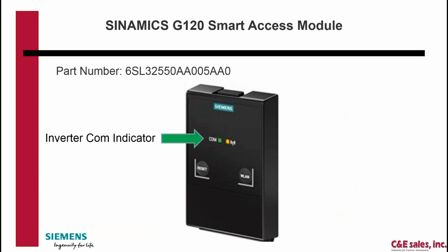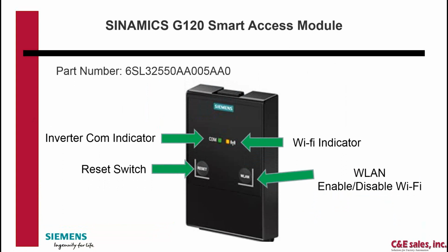So here's an up close look of what it looks like. You've got an inverter COM indicator, green, that shows you communication from the access module to the drive. There's a Wi-Fi indicator light for when you have Wi-Fi connected or not. The reset switch you have to hold in for a certain amount of time; that's going to reset the password of this module. And the WLAN button enables or disables Wi-Fi. We can turn off Wi-Fi by holding it in, I think it's 3 seconds.